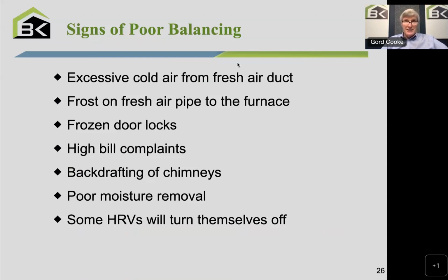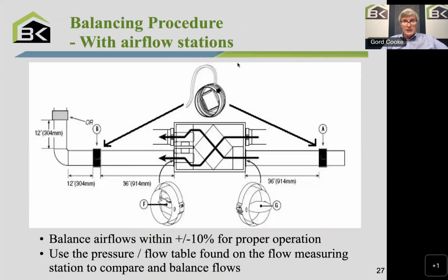So these are all signs that something's wrong with the unit, and it could be a balancing issue. It might be a control issue or something, but it could be a balancing issue. And so here is the procedure. You have this flow measuring station, as I mentioned. You install one in the exhaust airstream, one in the supply airstream, and you take a measure with a gauge that shows that the airflow is the same in both locations.